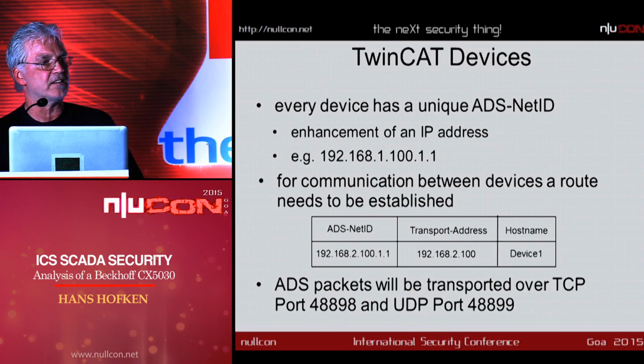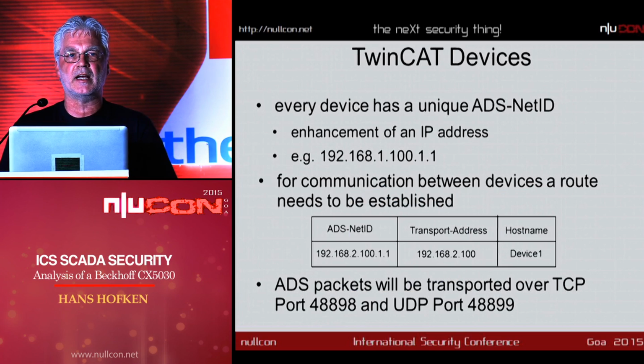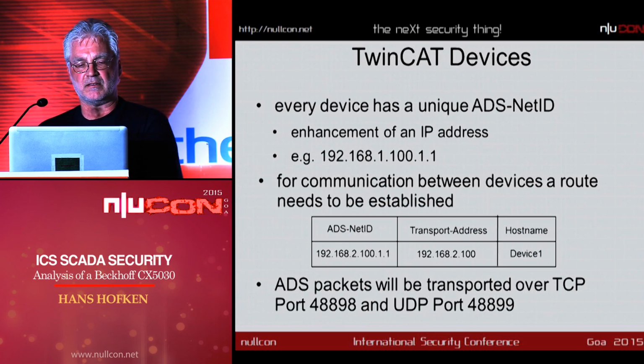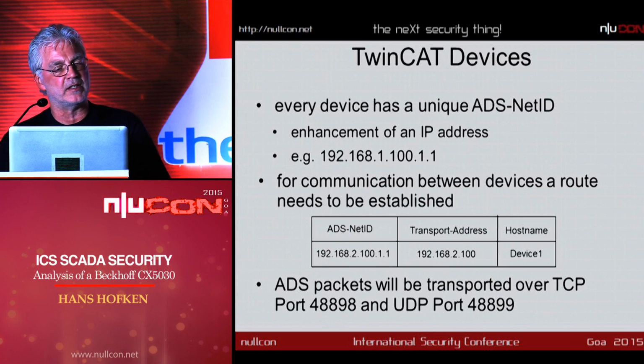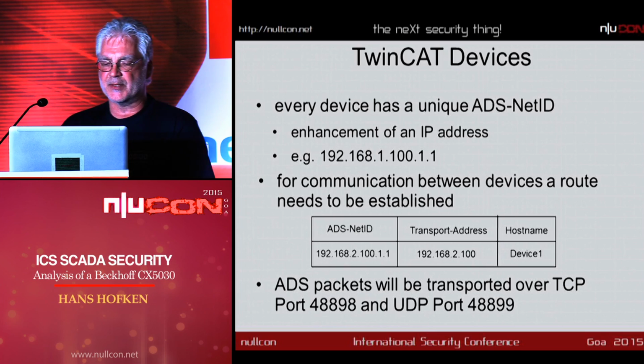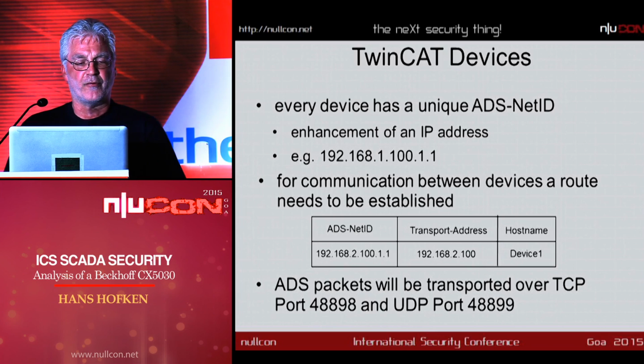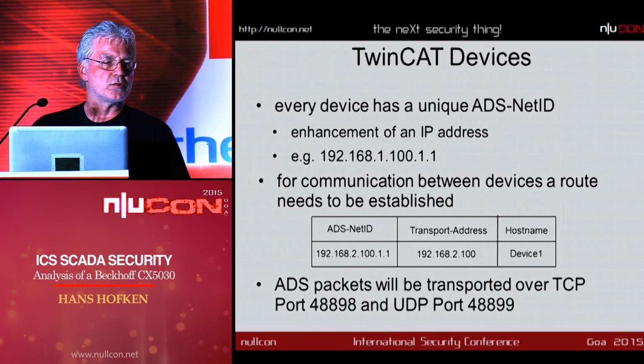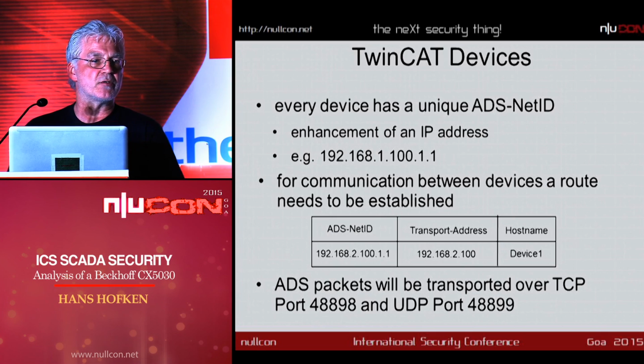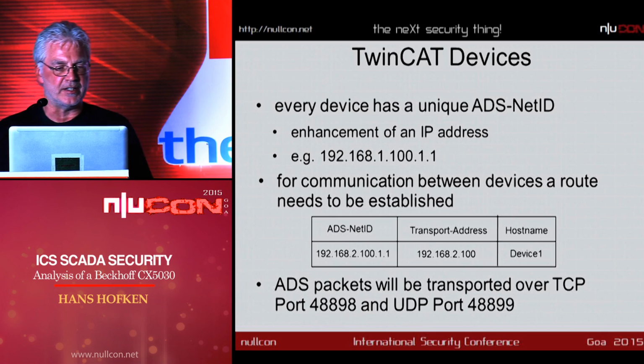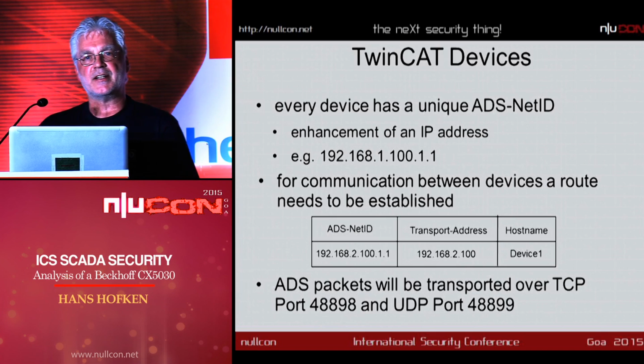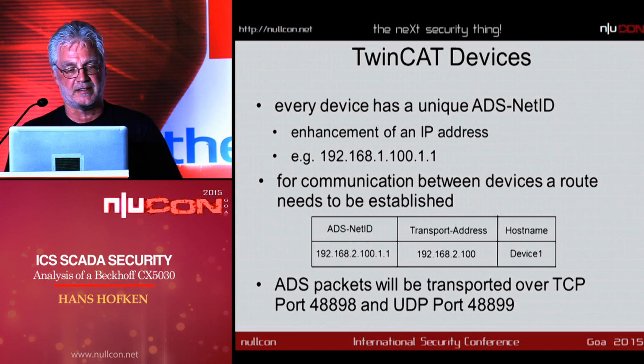The TwinCAT devices—TwinCAT is the management software for the SCADA system and the PLCs—have a unique net ID, which you need if you want to communicate with the device. The net ID is an enhancement of the IP address: the first four numbers are the usual IP address, and then two more numbers together with the IP address build the net ID. You have to know this net ID to communicate with the device.